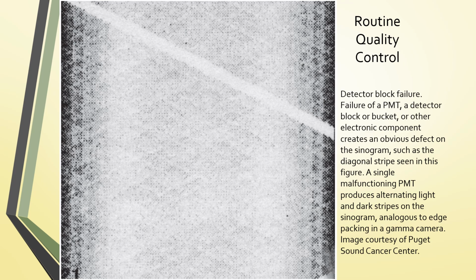This is an example of a detector block failure. This is failure of a PM tube, a detector block, or a bucket, or other electrical component that creates an obvious defect on the sinogram. So even though we say malfunctioning PM tube or detector block, keep in mind that those are electronic components. And if the electrical supply to them, high voltage supply, any of that circuitry in there is disrupted or malfunctioning, then it won't work either. So it'll look very similar. But a single malfunctioning PM tube produces alternating light and dark stripes on the sinogram. And this will kind of look like edge packing.